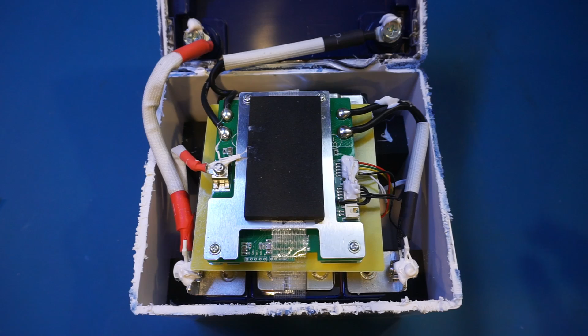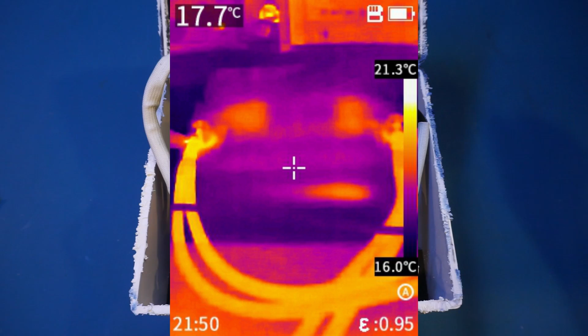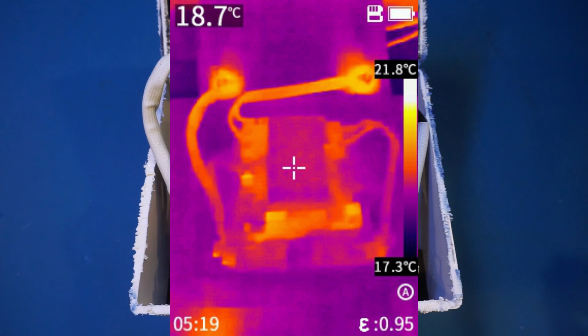Originally I thought the BMS was towards the side of the case, as from the thermal image earlier I saw a slightly warmer spot on the side. But you can see the BMS is actually right in the middle here. I just charged up the battery, and during charging the BMS actually stayed relatively cool. So I think what we were seeing earlier was perhaps from the wiring touching the case. The wiring did get a little warm during charging, but that's not because of the capacity of the wiring, rather it's the heat conducted through the terminal from the charger clamp.